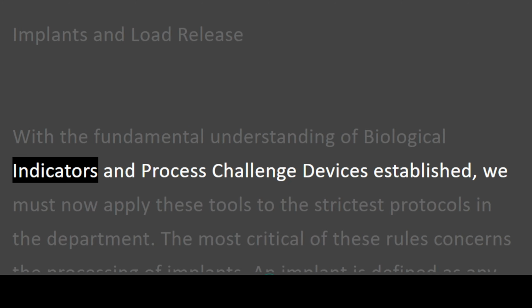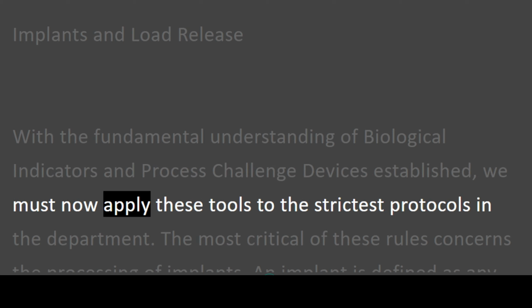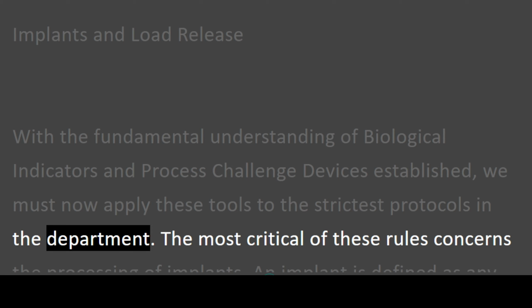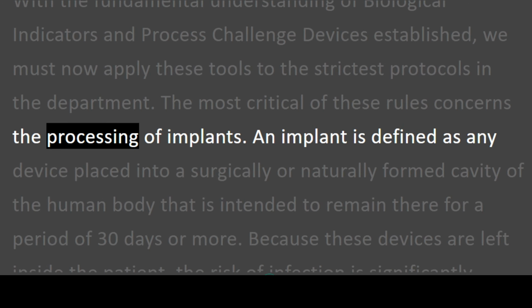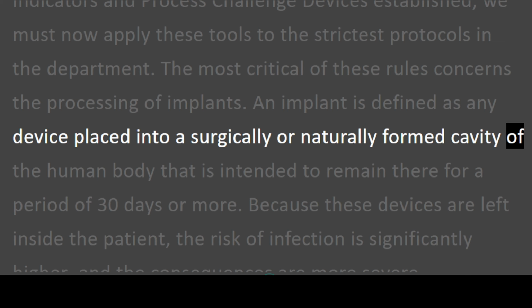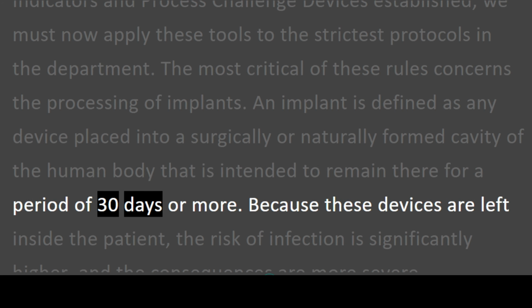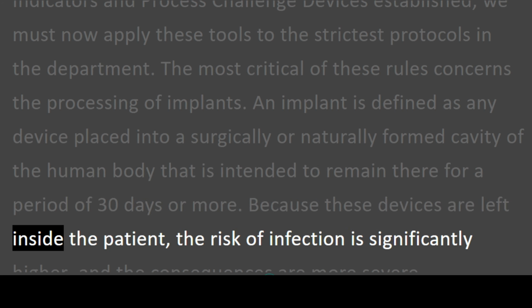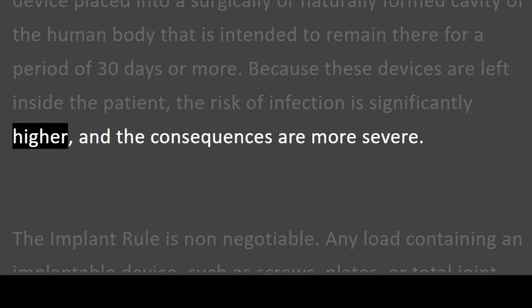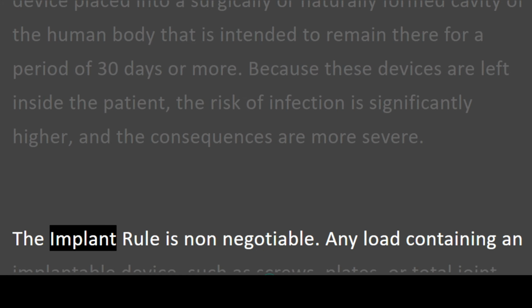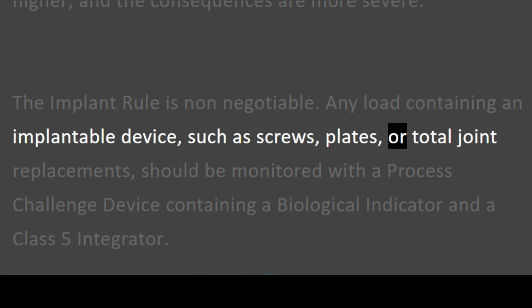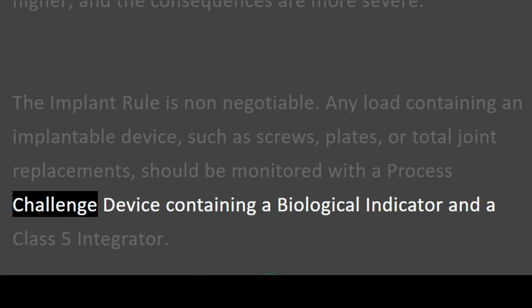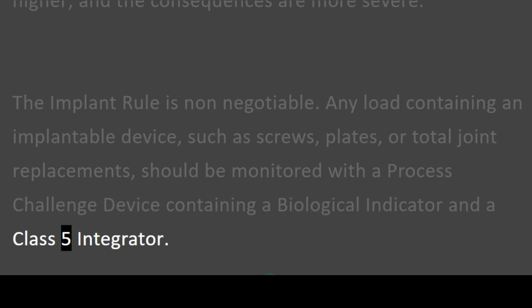Implants and load release. With the fundamental understanding of biological indicators and process challenge devices established, we must now apply these tools to the strictest protocols in the department. The most critical of these rules concerns the processing of implants. An implant is defined as any device placed into a surgically or naturally formed cavity of the human body that is intended to remain there for a period of 30 days or more. Because these devices are left inside the patient, the risk of infection is significantly higher, and the consequences are more severe. The implant rule is non-negotiable. Any load containing an implantable device, such as screws, plates, or total joint replacements, should be monitored with a process challenge device containing a biological indicator and a Class 5 integrator.